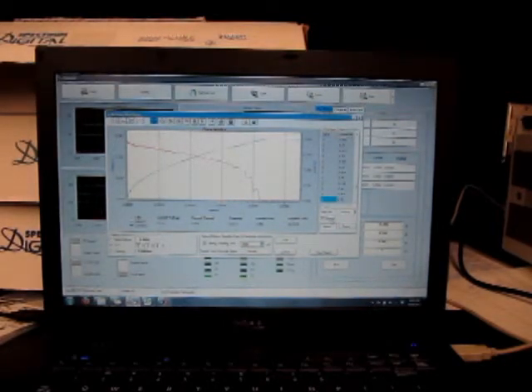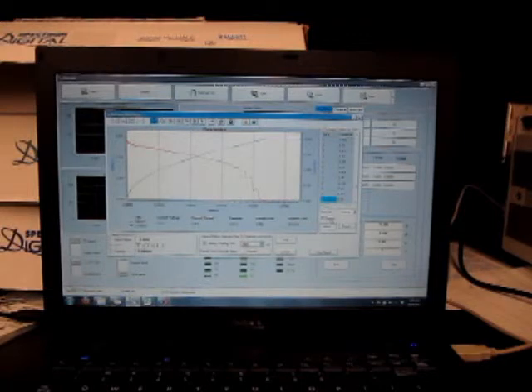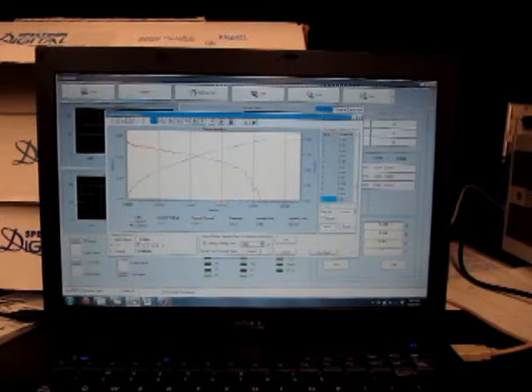You can go back to the battery discharge and just click on repeat if you want to do two in a row. Or if you want to append to another sample. So I've already done one, sample one, but I want to add another one to it. That'll go into the same Excel file. So when I hit start, it'll go through the test and then view report.